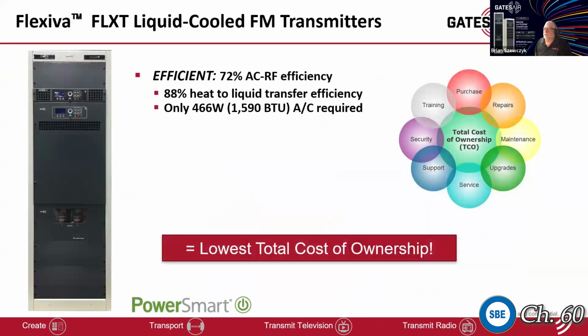So the transmitter itself is going to be very efficient. It's typically 72%, and because we're offloading the majority of the heat, a typical 10 kilowatt unit is going to put in about 1,500 BTUs of heat into the room, thus minimizing your air conditioning requirements.